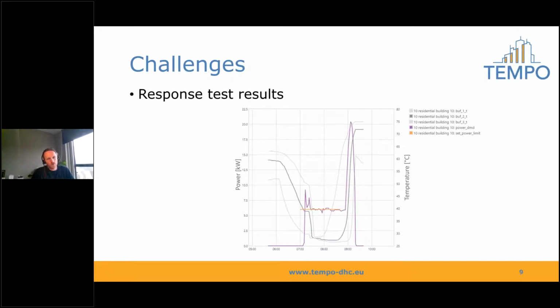So we wanted to charge the buffer at a slow rate, so 6 kilowatts. But what you see here is that at 7:30, for example, there's a high demand for hot water, so the buffer temperature drops immediately. Because we have our 6 kilowatt limit here, the buffer is not able to recover from that. Normally the buffer should start charging here at full power, but because we put the limit, it doesn't do that. So this can lead to having a cold shower, which is of course something we would like to avoid.